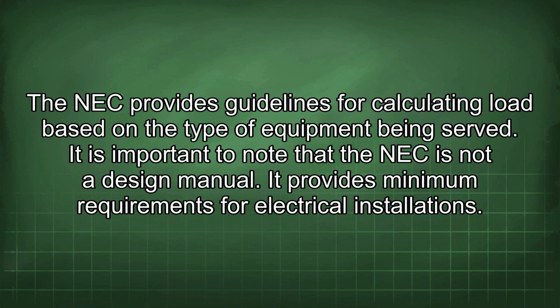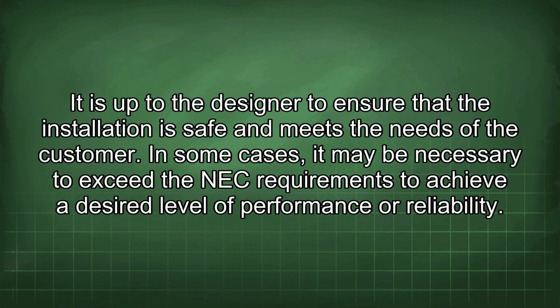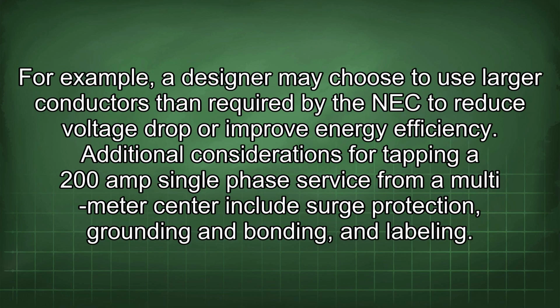It is important to note that the NEC is not a design manual. It provides minimum requirements for electrical installations. It is up to the designer to ensure that the installation is safe and meets the needs of the customer. In some cases, it may be necessary to exceed the NEC requirements to achieve a desired level of performance or reliability.